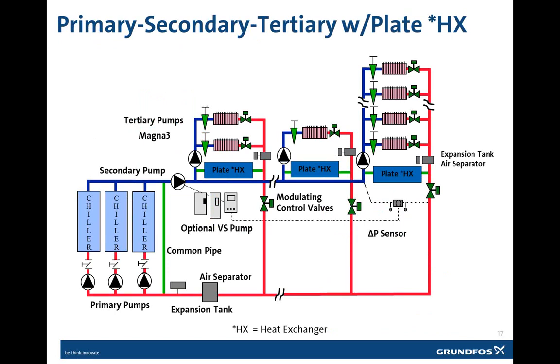Now, primary, secondary, or tertiary designs could also be designed with plate heat exchangers. The plate heat exchangers replace the secondary, tertiary common pipe. If we look at the design from earlier, the principle for primary secondary piping means that changes in pressure or flow in the primary will not cause changes in the pressure or flow of the secondary, and vice versa. So the plate heat exchanger represents the perfect common pipe. At no time can the flow or pressure change on one side of the heat exchanger affect the flow or pressure on the other side. It's just used as a heat transfer device only. Shown here is a simplified schematic showing a plate heat exchanger in place of the common pipe. Some of the accurate piping details are shown in more detail in later slides.